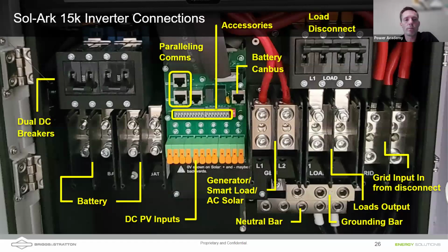We do have combiner bars, and we have trainings out there and an integration guide out there to help you navigate the connections here. These are the DC solar inputs, the MPPTs, the 3 independent MPPTs, each having 2 positive and 2 negative connections for paralleling at the inverter. So AC coupling would come through this gen port where the neutral bar is down here in the back bottom.